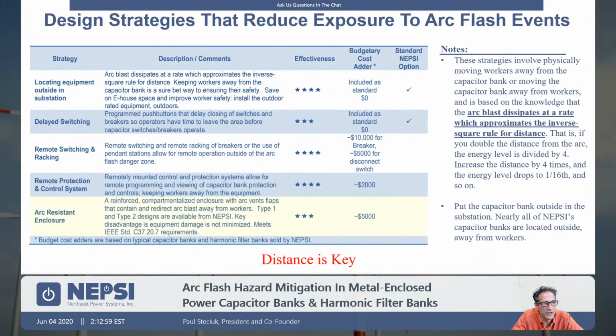So we have many different design strategies, and we have a table, and this is a document that was produced by NEPSI. It can be found on our website. But these are design strategies that reduce the exposure to the arc flash event. And again, where you locate the equipment is important. Delayed switching: we install delayed switching on our on-off auto switches. If we put the bank into manual mode, it allows the operations person to step away from the equipment and allow the system to energize while the person is standing away from the equipment. It's very simple and has no cost adder. Basically, turn the switch on, walk away, it switches.